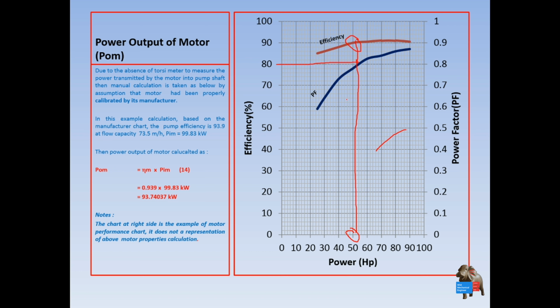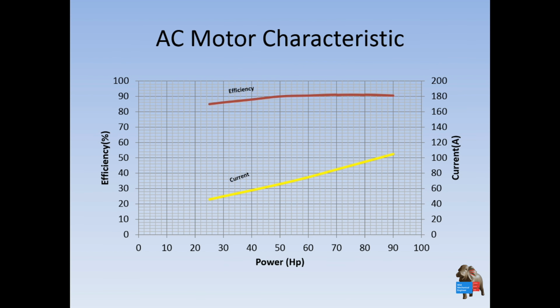So it means the power out of the motor is not equal to the power in. There are losses there. That is why you need this graph, to know how much the motor actually transfers the energy to the coupling, and from the coupling to the pump shaft. Okay, this is another characteristic of the AC motor that you need to know.